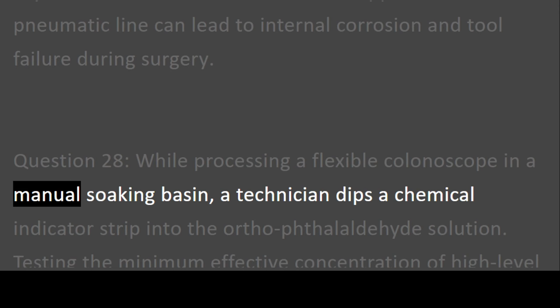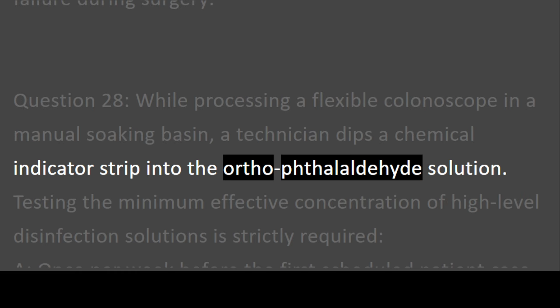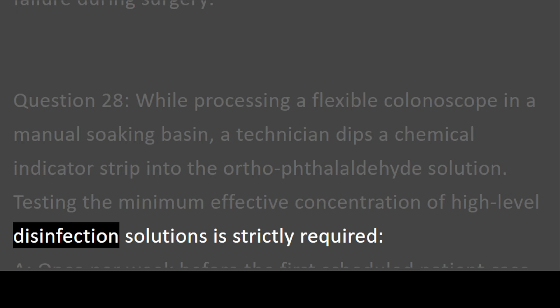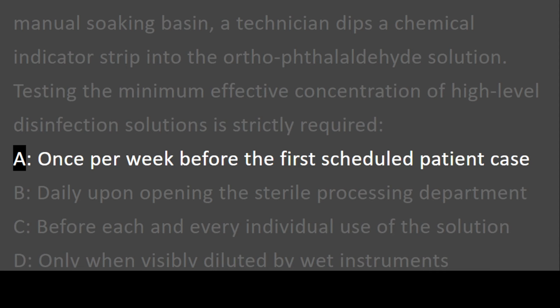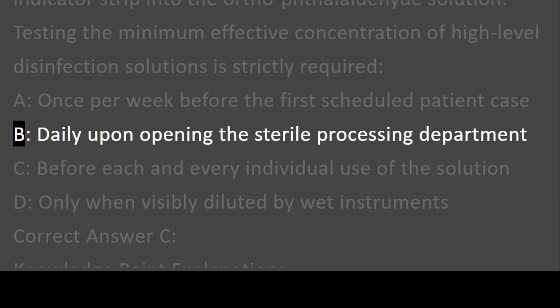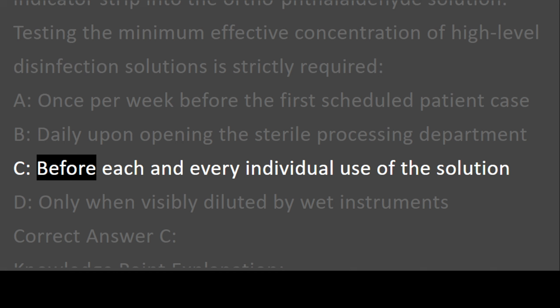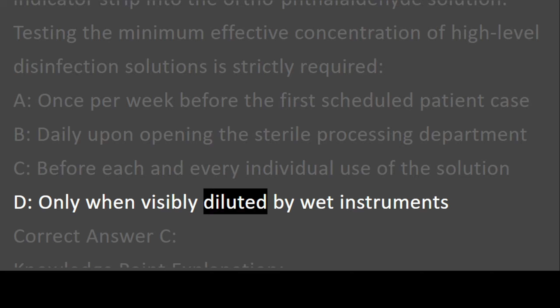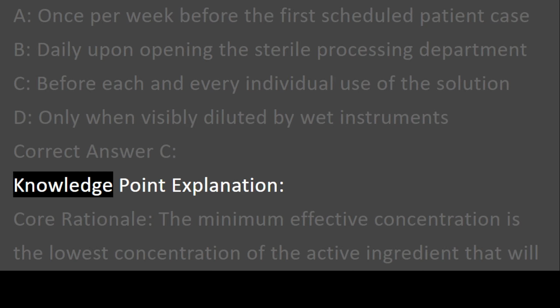Question 28. While processing a flexible colonoscope in a manual soaking basin, a technician dips a chemical indicator strip into the orthophthalaldehyde solution. Testing the minimum effective concentration of high-level disinfection solutions is strictly required. A. Once per week before the first scheduled patient case. B. Daily upon opening the sterile processing department. C. Before each and every individual use of the solution. D. Only when visibly diluted by wet instruments. Correct answer C. Knowledge point explanation.